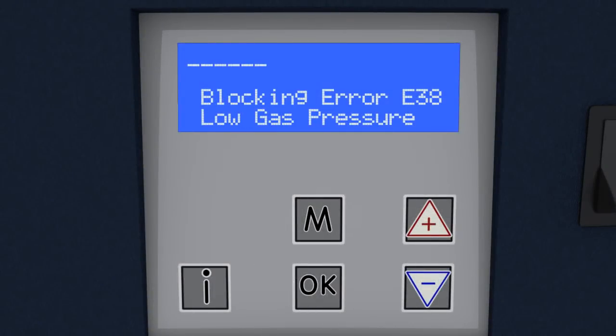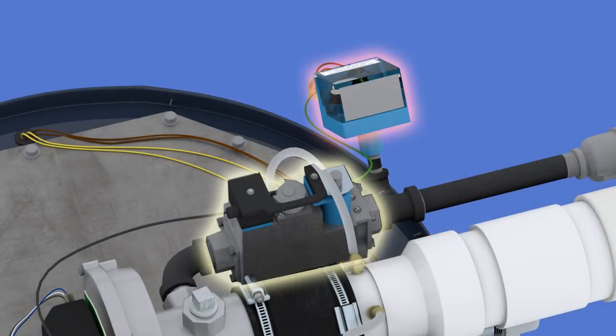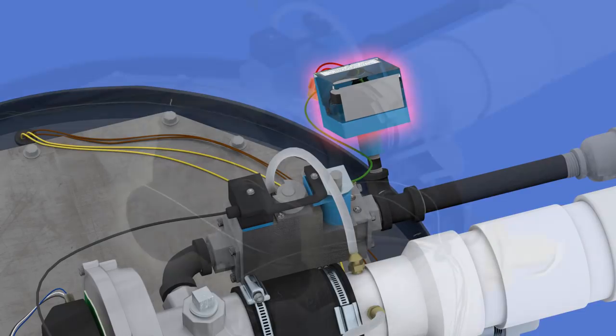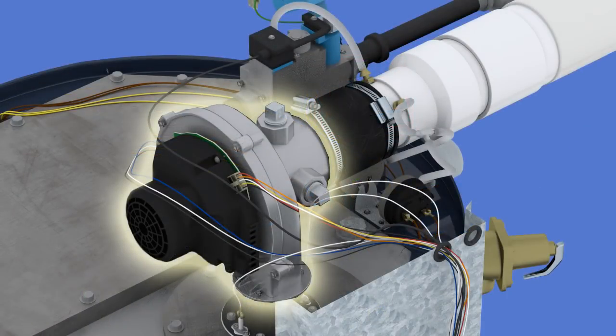If low gas pressure is detected at startup, an E38 blocking error code is displayed, and the unit stays in standby until the error is cleared. If low gas pressure is detected during a run cycle, the gas valve is de-energized and the blower goes to a post-purge speed for 25 seconds. The blocking error code is displayed and the unit stays in standby until the error is cleared.